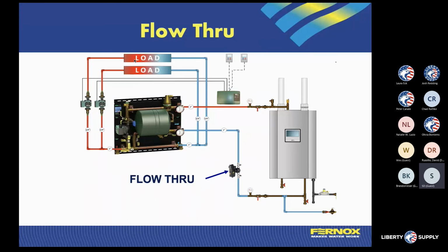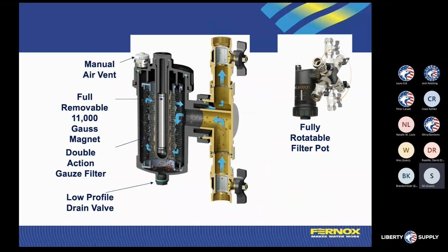So in those types of applications where we're doing what we call a direct or a flow through, we're putting that system right on the return from that standpoint, so that you can have that filter be 100% of that flow. If you have a system where you can't be down or you can't shut it down, that's where the difference between bypass and flow through comes in. Again, it's just the amount of time that you can have that system down so that you can clean that assembly and put it back together. All of the guts are essentially the same. Even if they plug up, you will get some flow, but it will reduce. And then we'll talk about the magnetism.